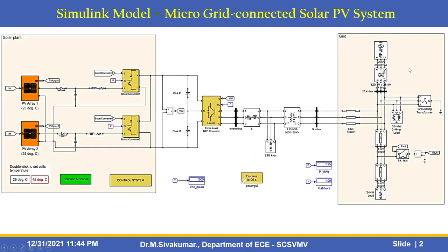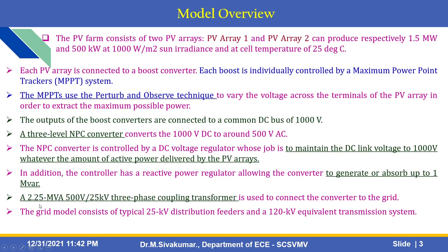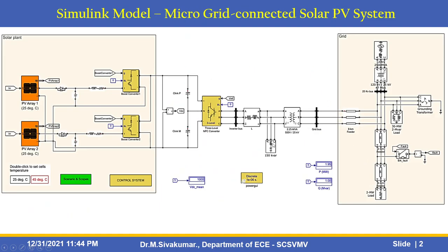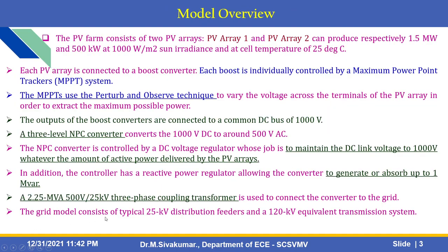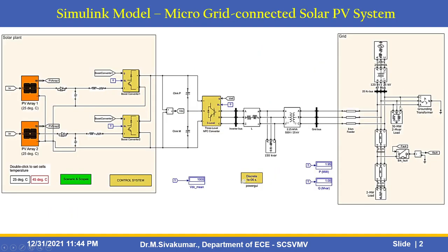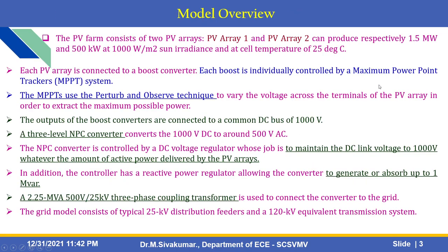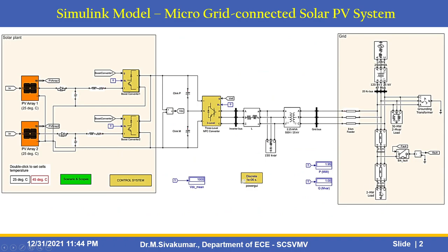A 2.25 MVA, 500 V / 25 kV three-phase coupling transformer is used to connect the converter to the grid. The grid model consists of a typical 25 kV distribution feeder and a 120 kV equivalent transmission system, and a 2 MW load. This is the Simulink model for the microgrid connected solar PV system.